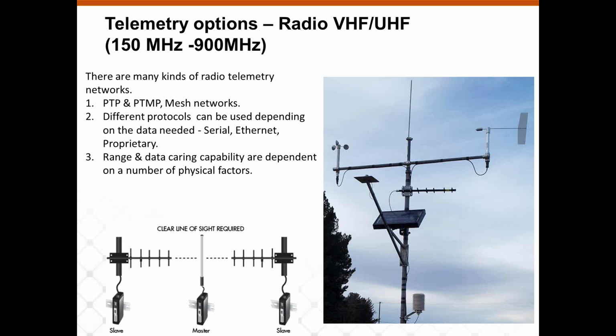Other instances of mesh would be a low-powered sensor network talking back to a gateway, and the gateway would, by several different means—either Modbus 485, OPC, or Ethernet—get that information back into the control system so it knows what's going on, and includes that information as part of the loop control they're doing in the process industry.